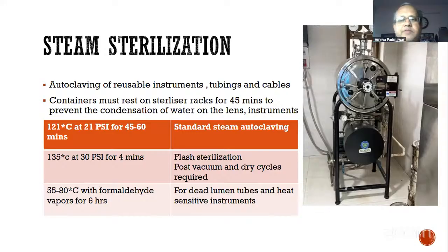So this is the one which is available in our office, and after the autoclaving cycle is over, the containers must rest for at least 45 minutes. This ensures the drying of all the instruments and prevents the condensation of vapor on the lens of the optical instrument. The standard steam autoclaving involves heating the steam to 121 degrees Celsius at a pressure of 21 psi for 45 minutes. This is a standard protocol and is sure shot and works for most laparoscopy and hysteroscopy instruments.